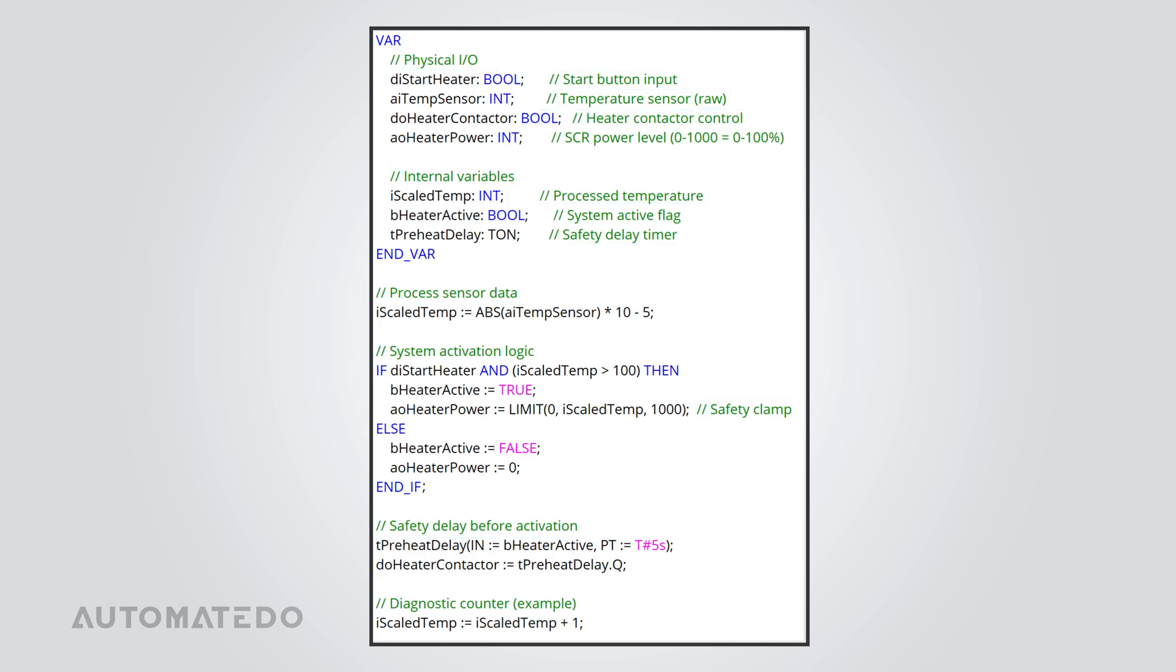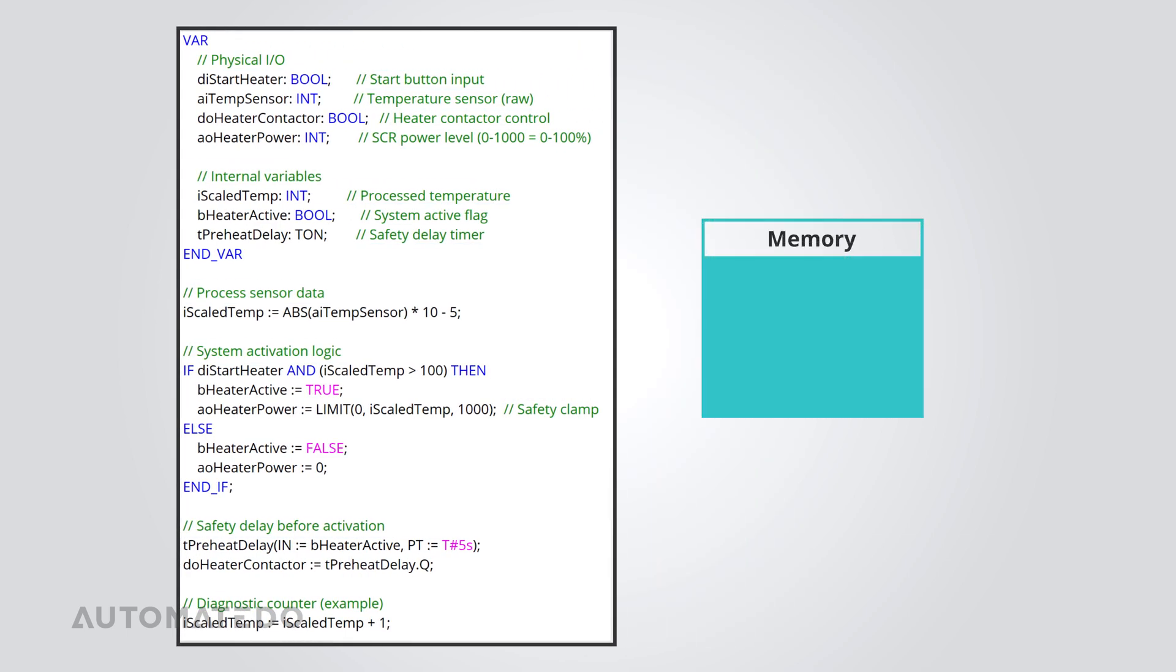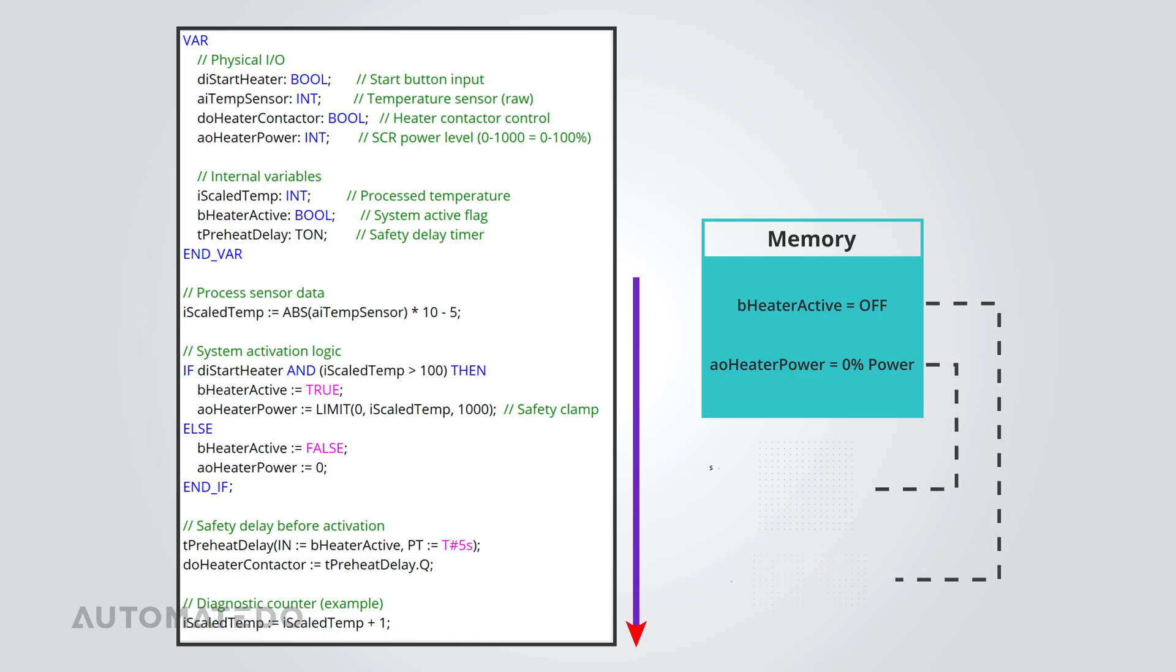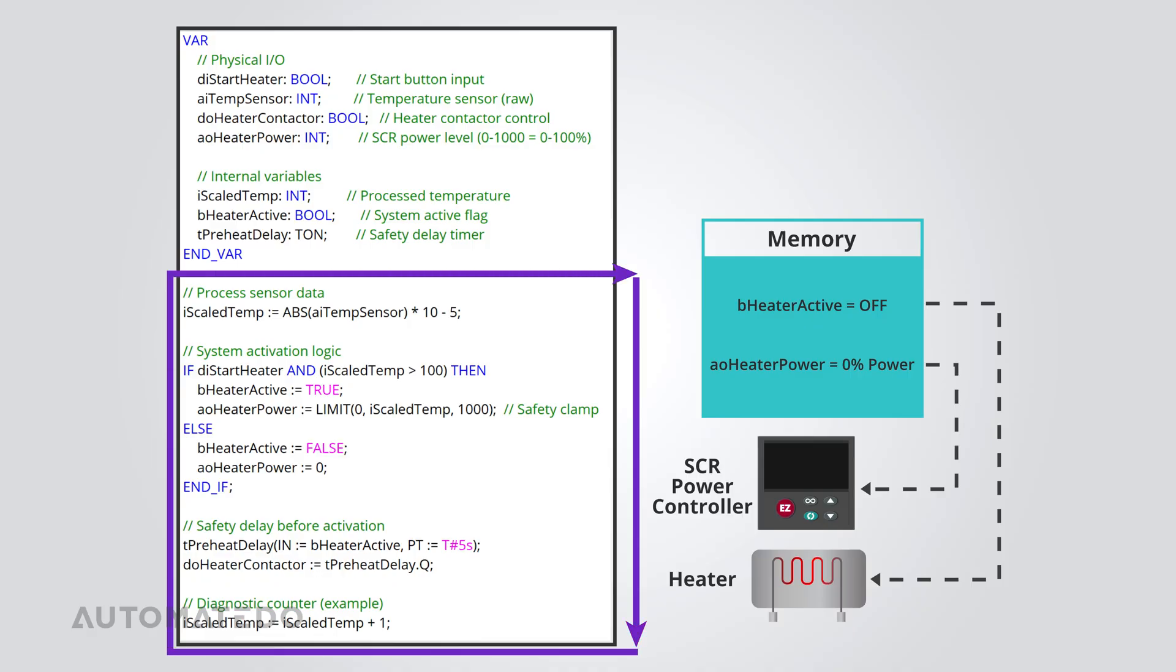Here's how an ST program runs inside a PLC. It's all about cycles that repeat nonstop. First, the PLC reads the input signals and updates the input variables. Then, it processes the ST code from top to bottom, temporarily storing output values in memory. At the end of the cycle, it writes those values to physical outputs, ensuring your system responds as needed. This loop keeps going indefinitely, keeping everything synchronized and predictable, essential for automation.